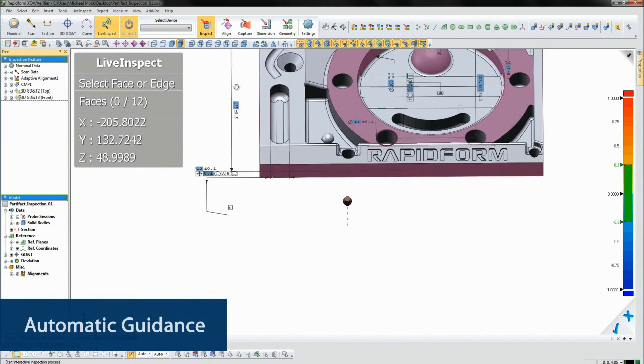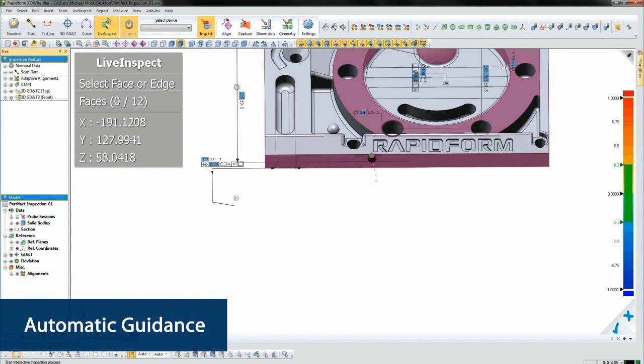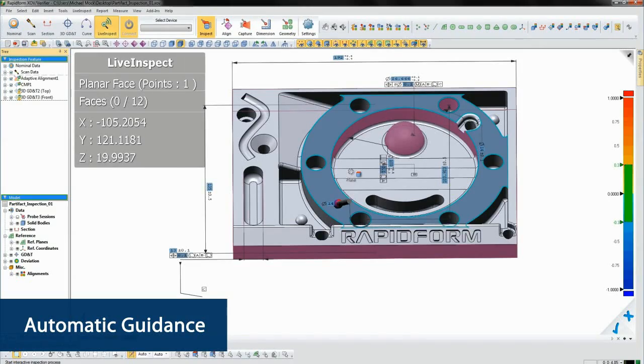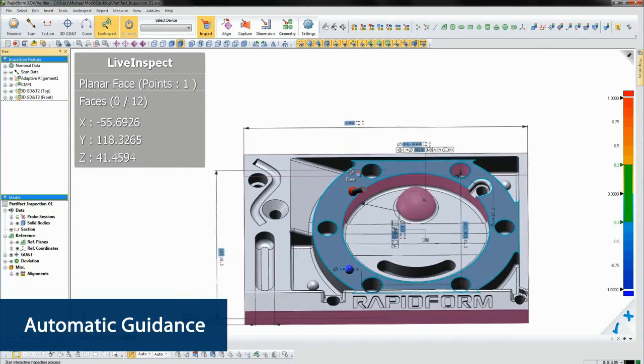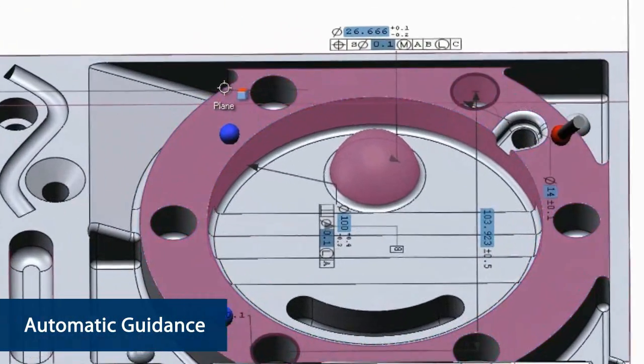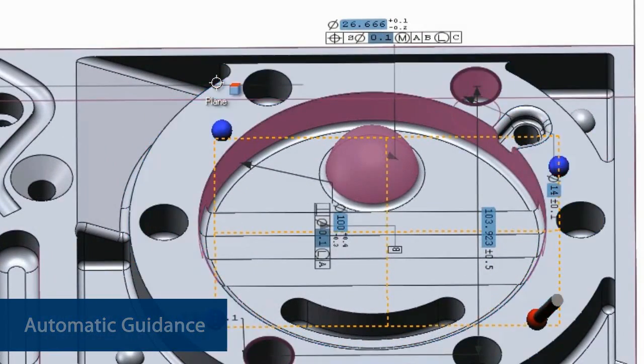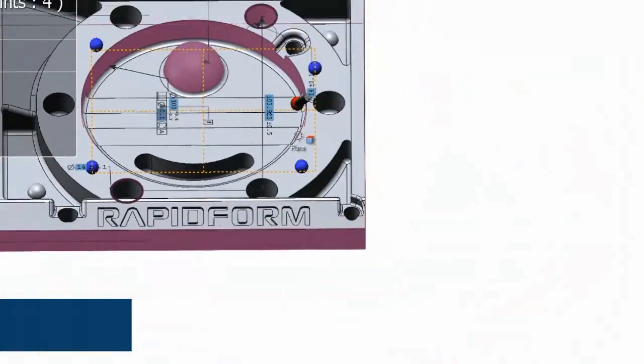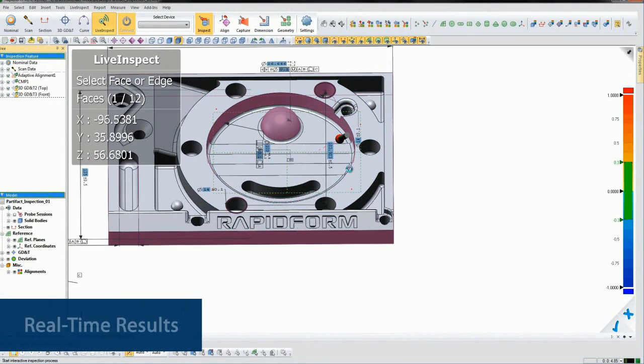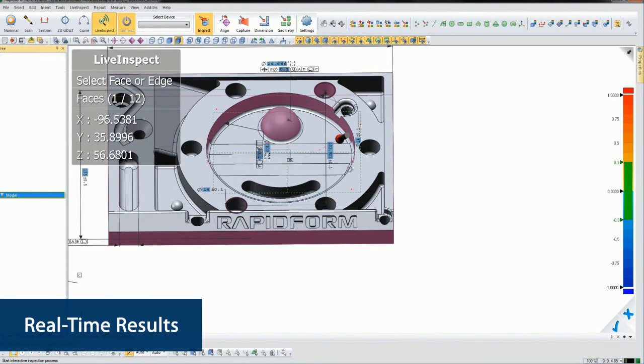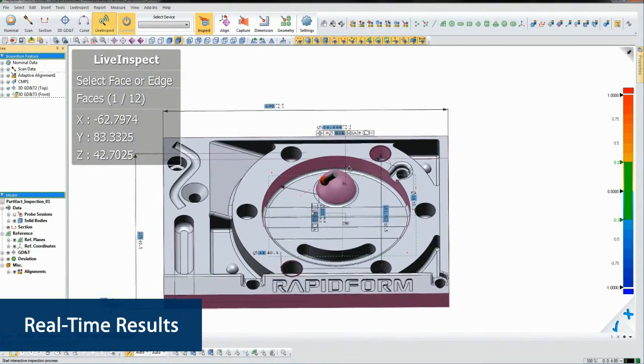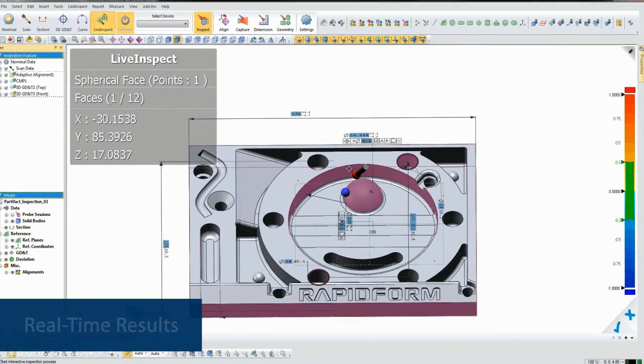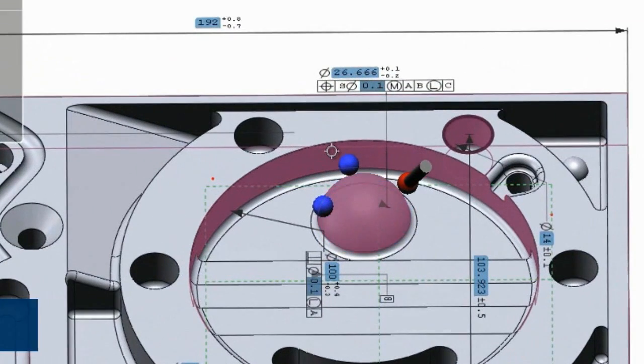Next, XOV will highlight faces on the nominal model that we need to probe. We just go in and probe each face in any order we want. The software will show the measurement results instantly. You can see as we probe each feature, the related GD&T callouts update in real time.